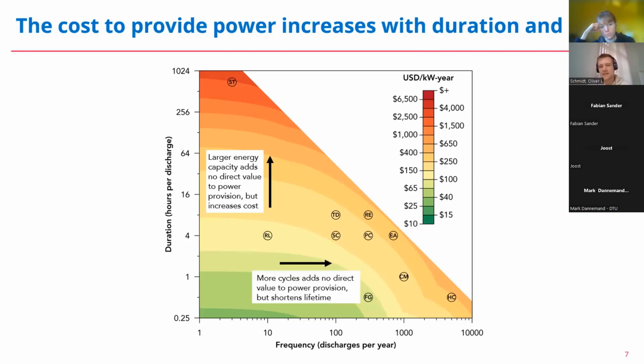The same applies if I have more cycles per year. I can still provide the same power, but because I have more cycles per year, I degrade faster, so the cost to provide the power increases. A common service, frequency regulation, would sit at around half an hour discharge duration and 300 cycles per year, in the cost range of $65 to $100 per kilowatt per year.